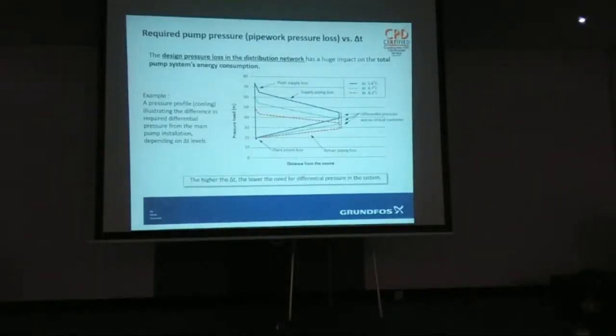We've done this in a little graph here, showing 3 different temperature differentials, 5.6, 6.7, 8.3. The blue one here requires more pressure at the pump to get a similar pressure out in the system. We're pushing more water down the line to maintain a narrower temperature range, so you've got a greater pressure distribution diagram through it. At the lowest one, the widest differential, we can start off with a lot less pressure at the pump, and a lot less pressure throughout the system to achieve the same differential out at the circuit. Keep the pipe resistances up and the valve sizes up.